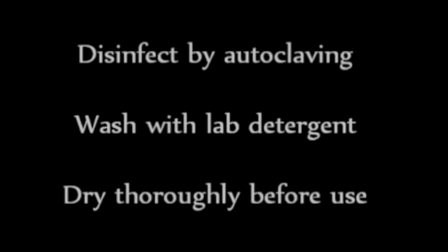The cryo grinder can be disinfected by autoclaving and cleaned with laboratory detergent. Thoroughly dry the mortar and pestle in a low temperature oven before using again. The cryo grinder must be free of moisture before it is chilled again.